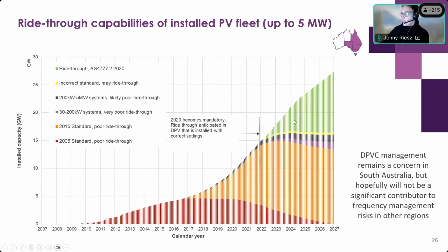This chart here is giving you an indication of our best estimate of what we think will ride through faults on the grid, looking at all systems installed up to a size of 5 megawatts across the whole NEM. So this is when the new standard became mandatory, the 2020 Australian standard with the new ride-through requirements. And you can see from that point onwards a growing proportion of systems being installed in the green. And this is installed capacity across the whole NEM. So we're tracking upwards of 20, 30 gigawatts of rooftop PV across the NEM. And this growing proportion that we do believe will ride through. These are our older systems on the 2005 and 2015 standards that we believe will have very poor ride-through capabilities.